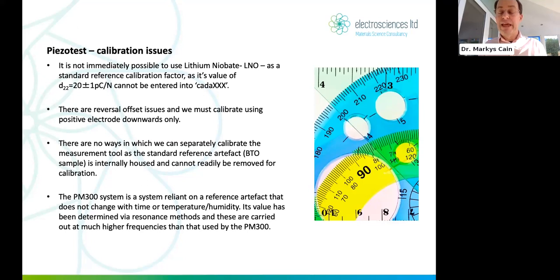Newton. Now, in the Piezotest machine, you're not able to enter that as a reference value. You've got to have something over 100. I mean, it's just the nature of the way it's working. So there's various ways around this, and I'll go through that in a slide or two. Reversal offset issues. It's very important to always have the positive electrode, in other words, the positive charge output electrode, down when you apply stress, okay? And that's because the top electrode is either earthed, or it's into a virtual earth, and that means you would typically experience offsets, which you don't want to experience in this case.